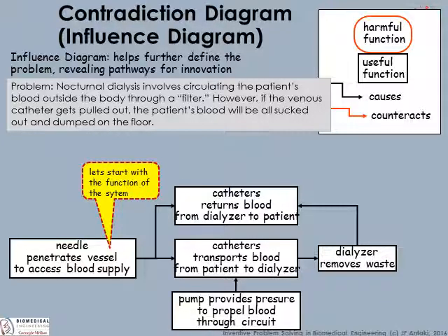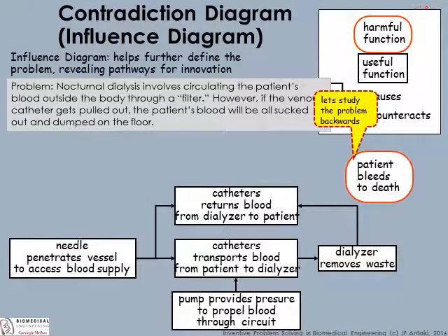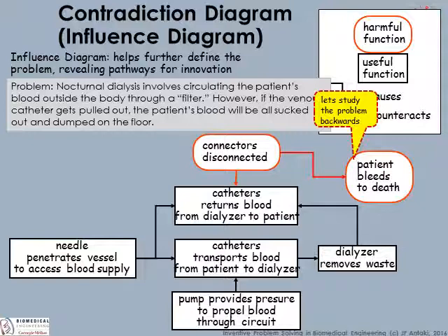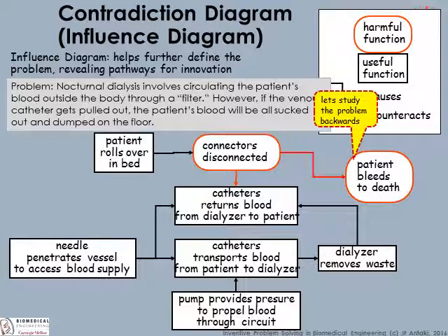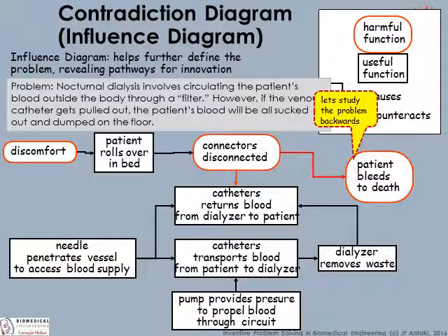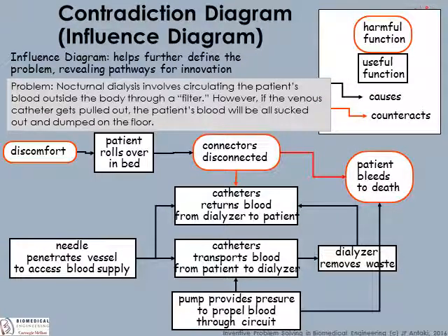The pump creates a pressure rise through the tubing to force blood through the pressure drop of the dialyzer and tubing. Here's the problem: we don't want patients to bleed to death. Studying this backwards, the patient is going to bleed to death if the catheter is pulled out of the body or the connectors become disconnected. Connectors might become disconnected if a patient rolls over in bed. Looking at this diagram, we might begin to see opportunities for innovation — perhaps in the patient's ability to roll over in bed, or something to do with the catheters being vulnerable to being pulled out, or something to do with the pump providing the pressure that causes blood to be sucked out.